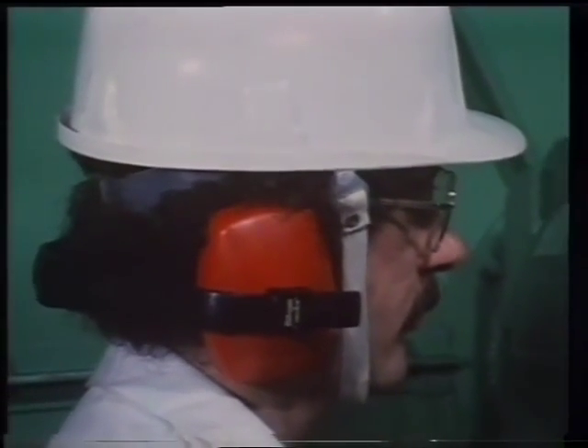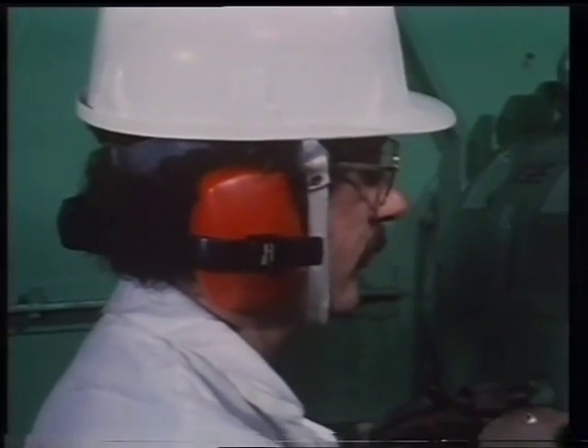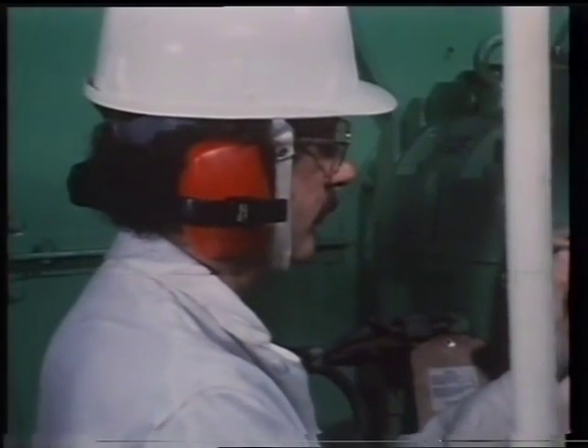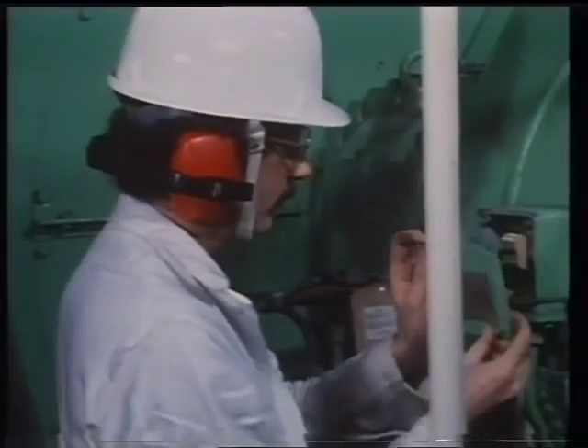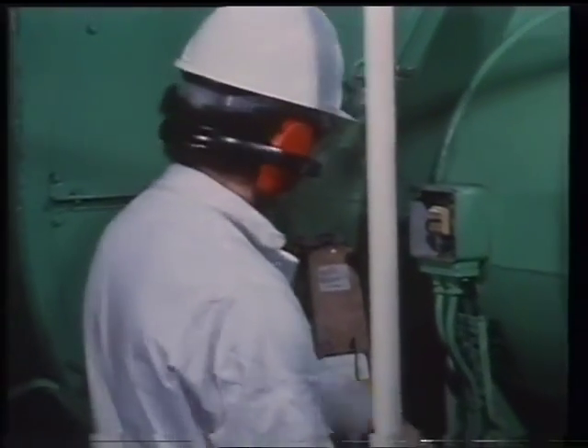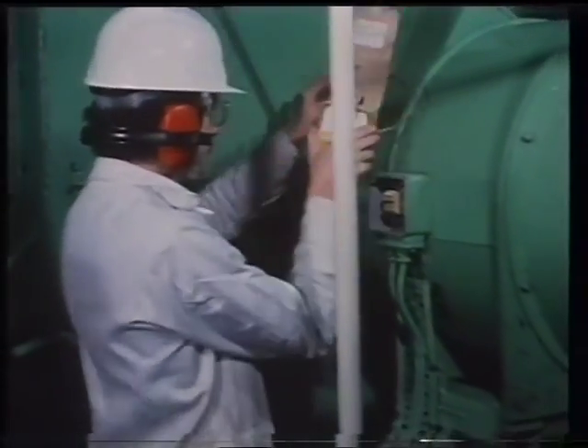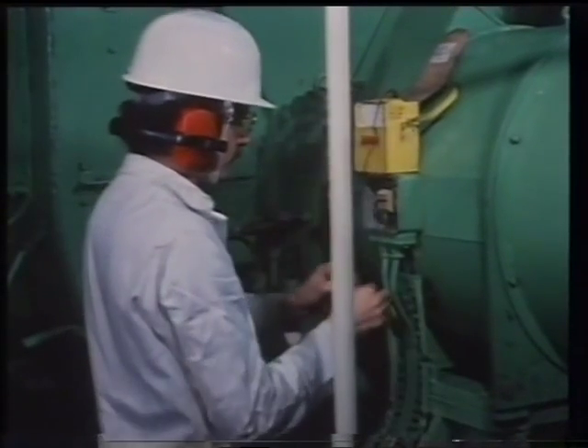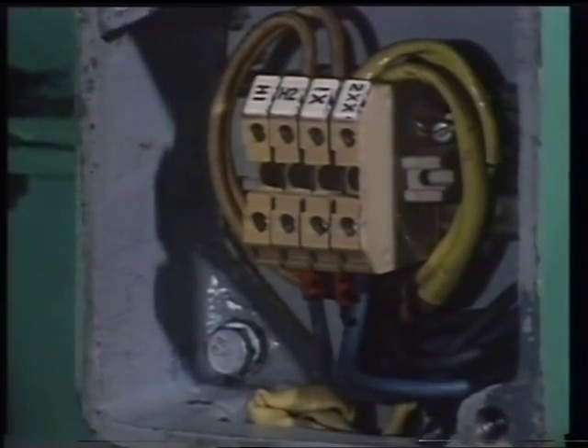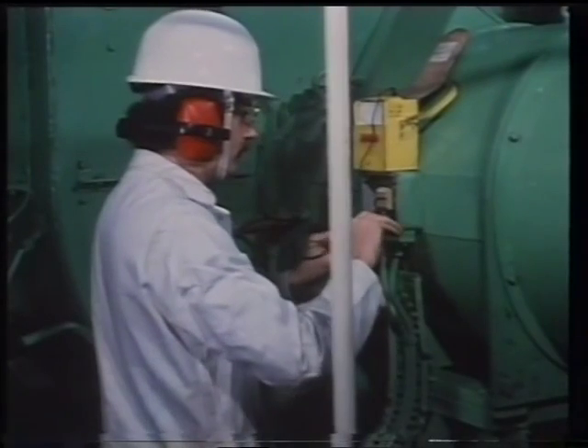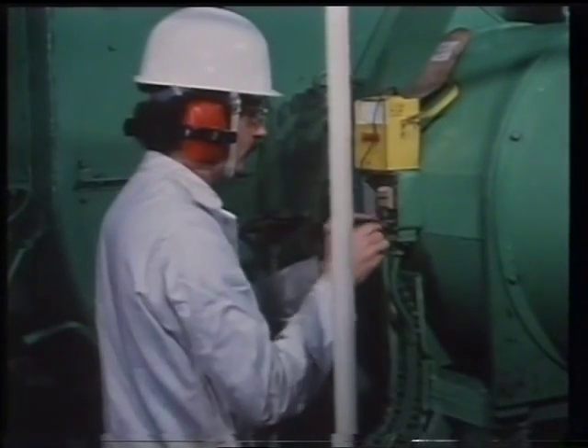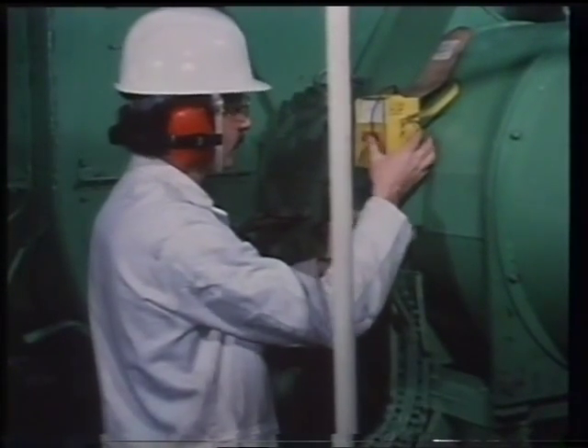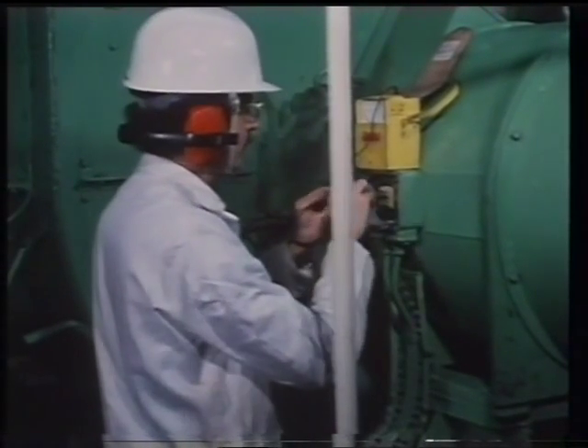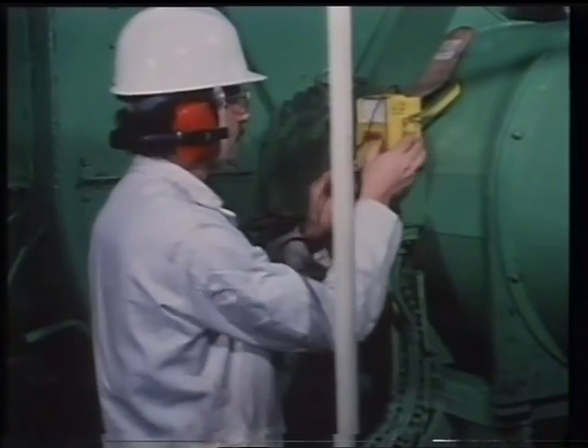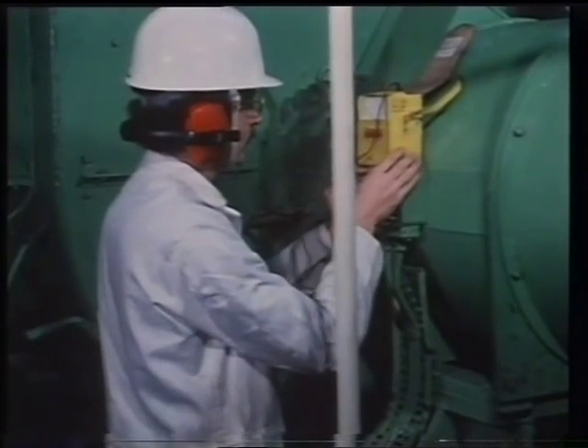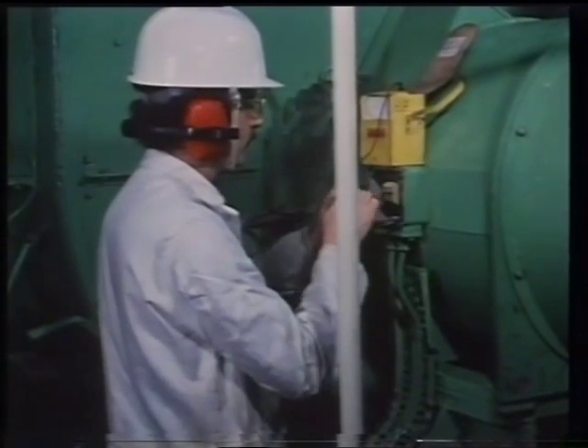Tests for possible faults in the exciter field coils are carried out at the terminal box. Here we see the coils being tested to earth. Again, the correct procedure is followed. First, the insulation resistance tester is checked, then 2 good earths found, then the test carried out.